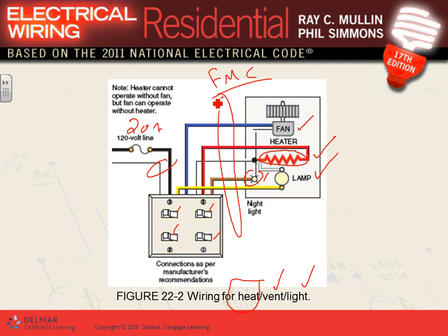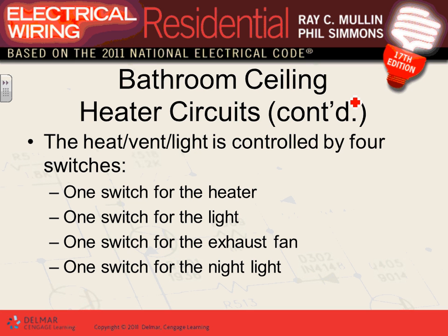Yes. So that's where a lot of the coordination happens when it comes to the mechanical equipment between us and the mechanical engineers. Okay, this is just this particular fixture. I can't emphasize this enough. It has a heat, a vent, and 2 lights, not just 1 light. So you have 1 switch for the heat, 1 switch for the normal light, 1 switch for the night light, and 1 switch for the fan. So how many switches do you need? 4 switches. You need a 2-gang box with 4 switches and a 2-gang cover, right? That's when you wire it.